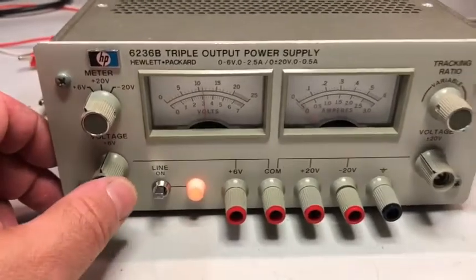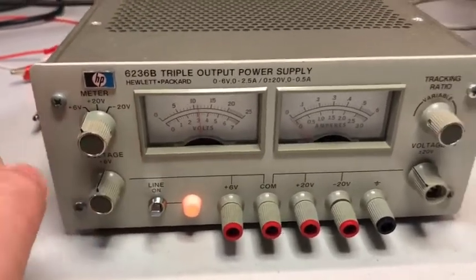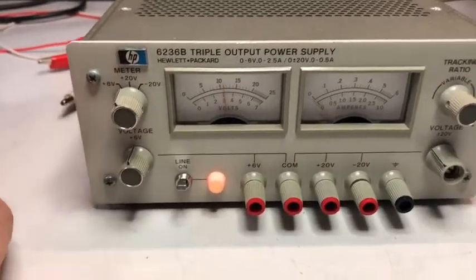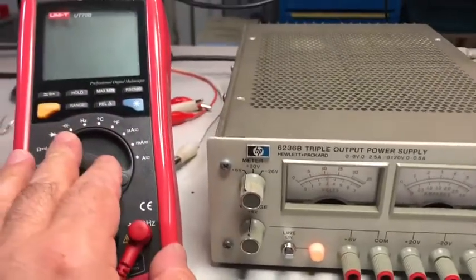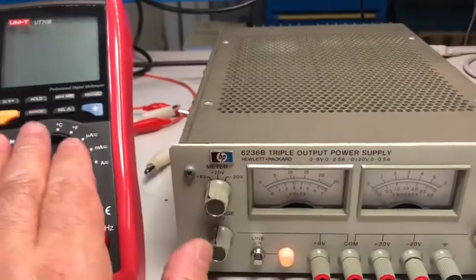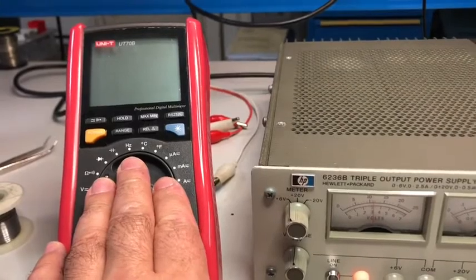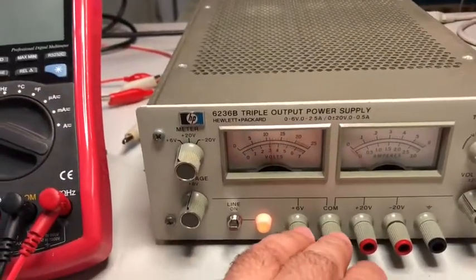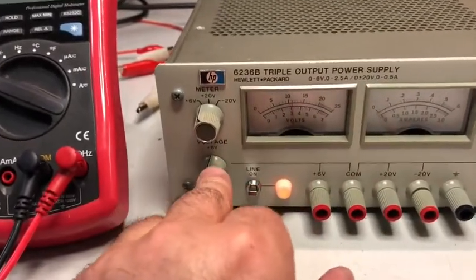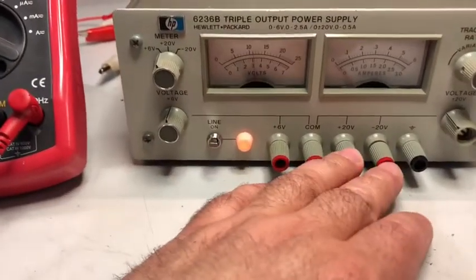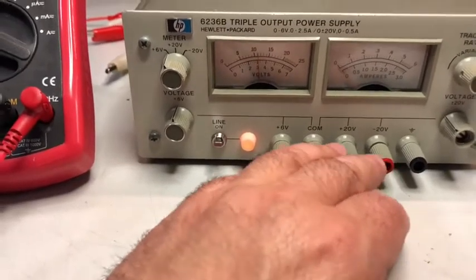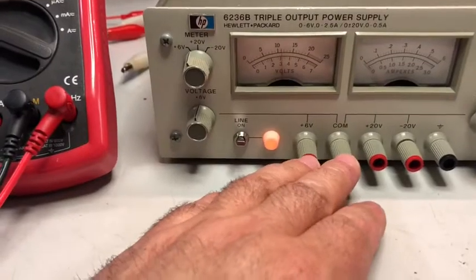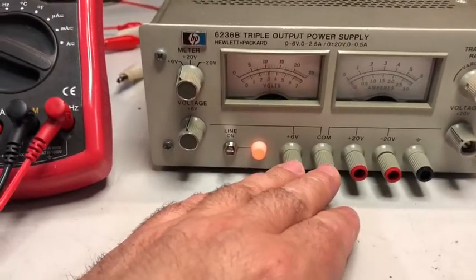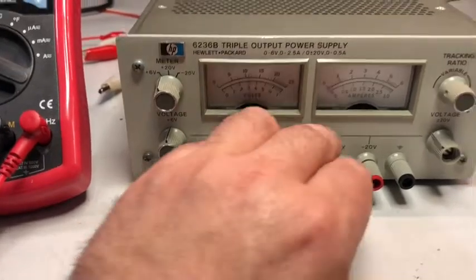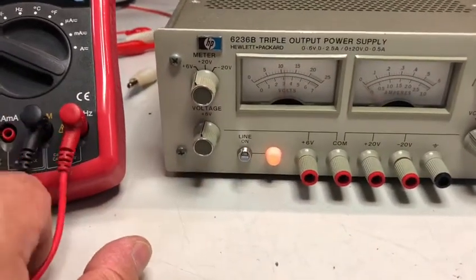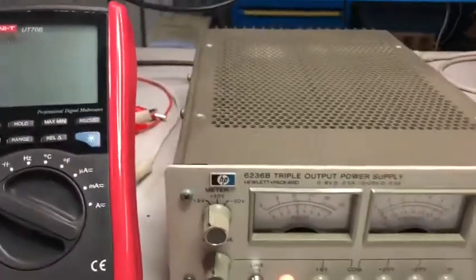After I checked the service manual, it's clear I was mistaken trying to regulate the maximum current with the ammeter connected directly to the output, since the 6 volt range works differently from the dual 20 volts. In fact, the 6 volt range, if it feels a dead short, will limit the current to 1 amp, and that was exactly what I was achieving during the test.